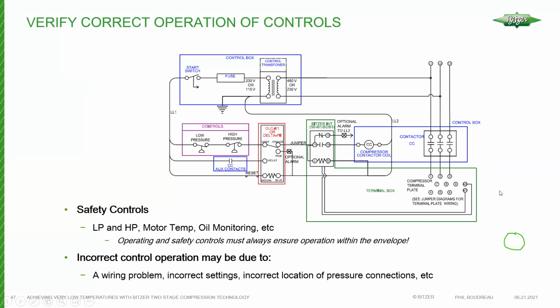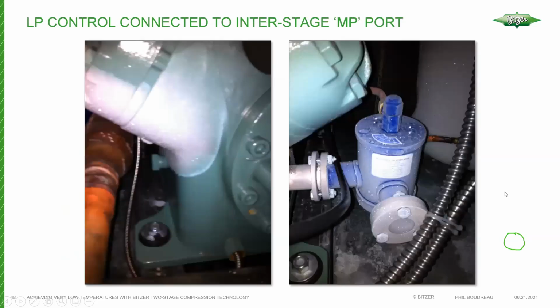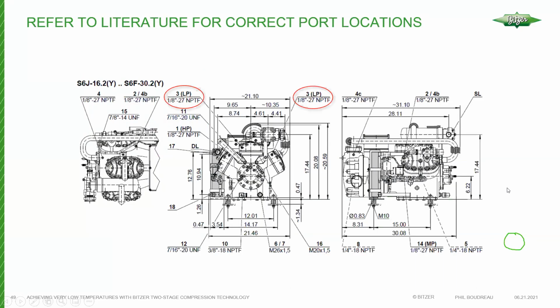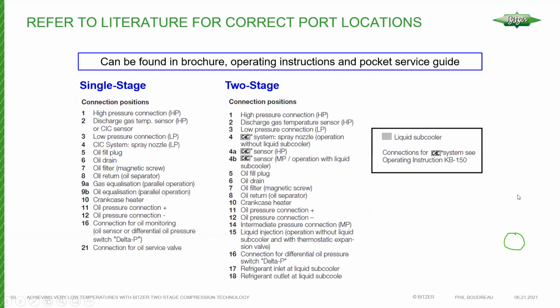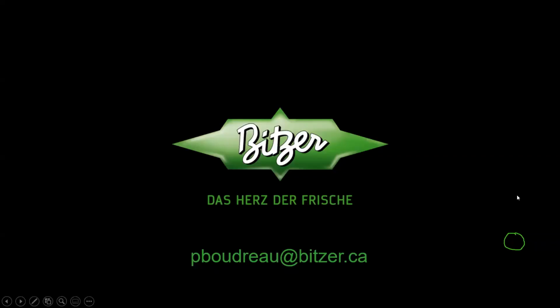Okay, and regarding controls, obviously we have to set the controls to protect the compressor and keep it in its envelope. But when you're connecting that low pressure control, I've seen this in the field where the low pressure control is actually connected to the interstage, and then we have a situation where the compressor never shuts off, even though there's no load on it. So you end up with a situation that looks like this, which is not very good for the compressor operation. Ports are indicated in the service manuals and the brochures. If you're not sure what a port is, you can look at the drawing. They're all marked, and then you'll have a legend that indicates what the various ports do.